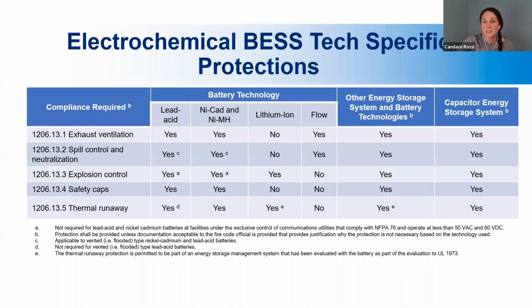So next is the electrochemical energy storage technology specific protections. Something this code really looks at is requiring different requirements based on the battery technology, and we'll go through each one of these compliances that are required. First, the lead acid battery. That requires exhaust ventilation, spill control and neutralization, explosion control, safety caps, and thermal runaway protection. Similar for the nickel-based batteries. Lithium ion does not have a requirement for exhaust ventilation or spill control.